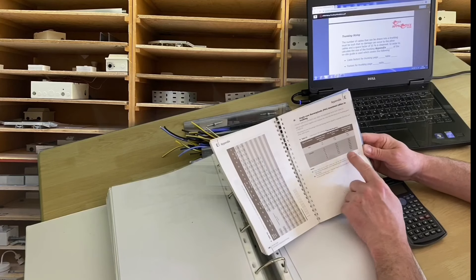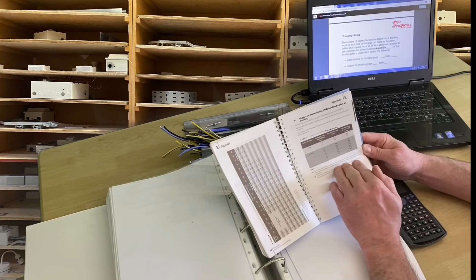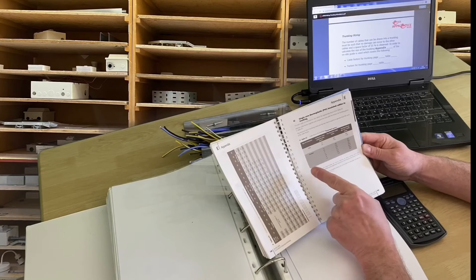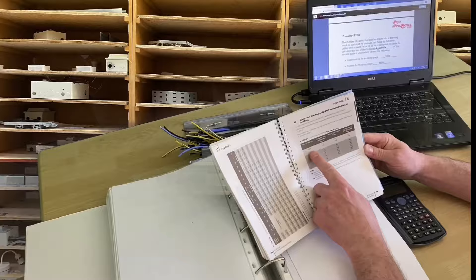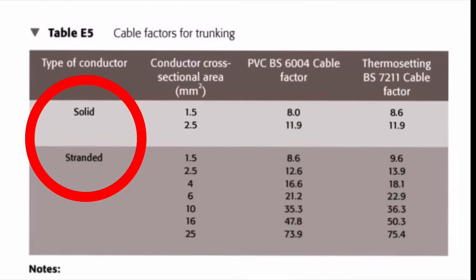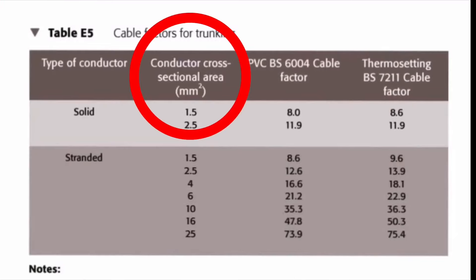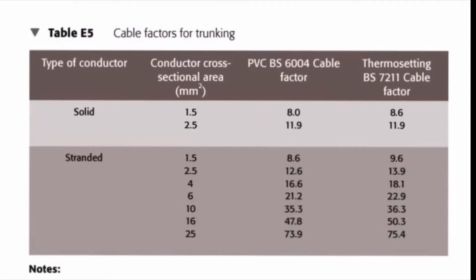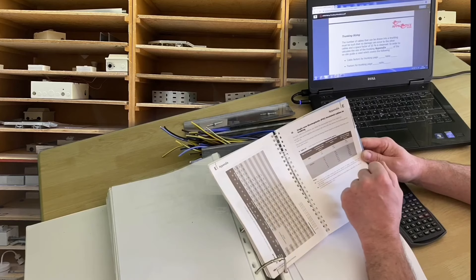Table E5 looks at the factor for the conductors in exactly the same way as when we were doing conduit sizing. First we have the type of conductors — whether solid or stranded — and in trunking and conduit systems we're always working with stranded cables. Then we have the cross-sectional area. Column three covers thermoplastic PVC — BS6004 cables — and the final column covers thermosetting PVC, an insulating material also found on singles.